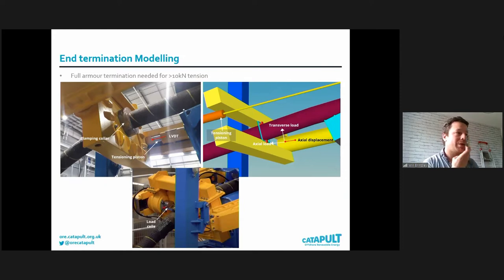And the end terminations here, we clamp the cable. So we apply some pressure to the cable and that stops it slipping under a sort of moderate tension around a ton. And luckily these cables are quite light and certainly in the near term, we're looking at fairly shallow water. So 100 meters, 200 meters water depth. Tensions are in the order of 1 to 5 tons. So we can reasonably well replicate the tensions that we need. If you want to go for higher tensions, that's possible, but you'd have to take the armor wires out and clamp them as you do in a cable end termination.